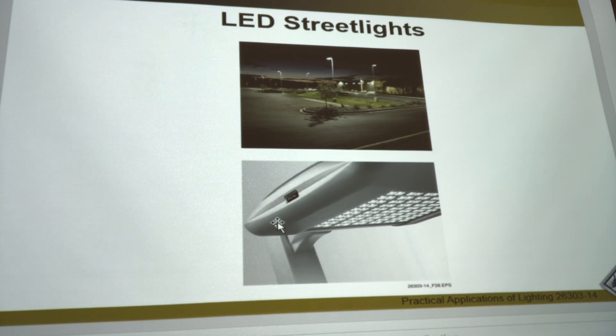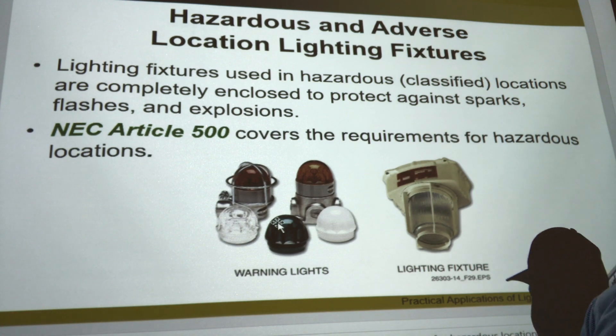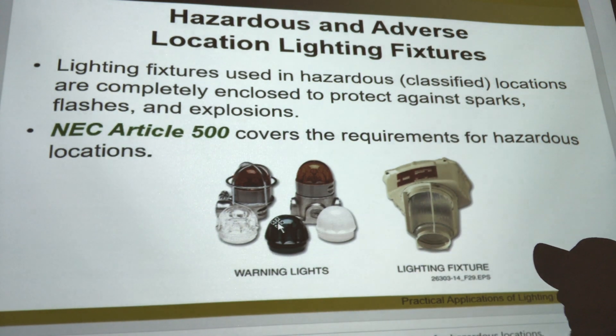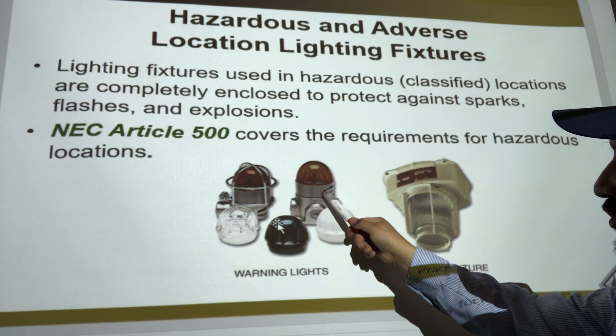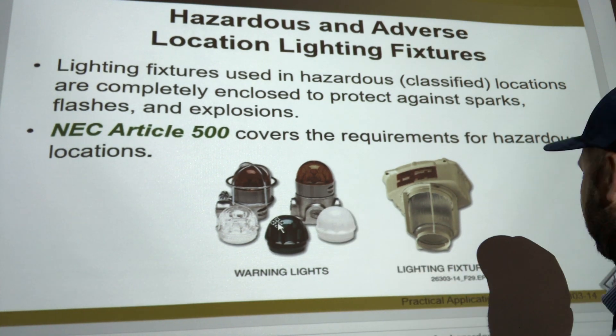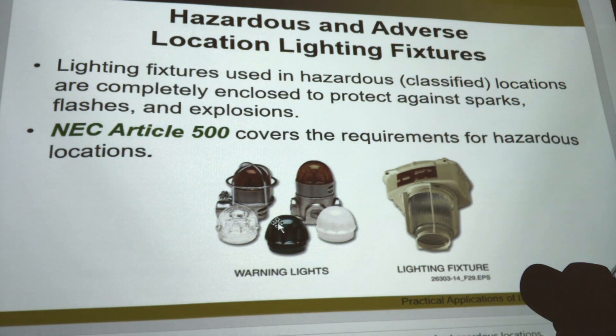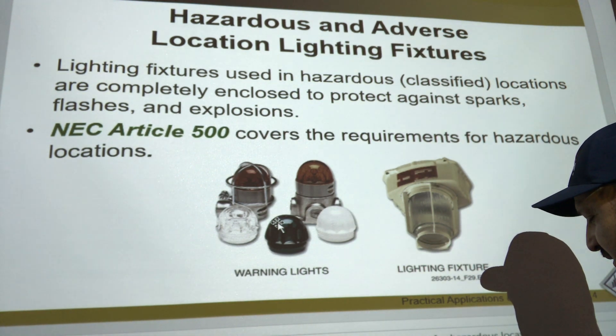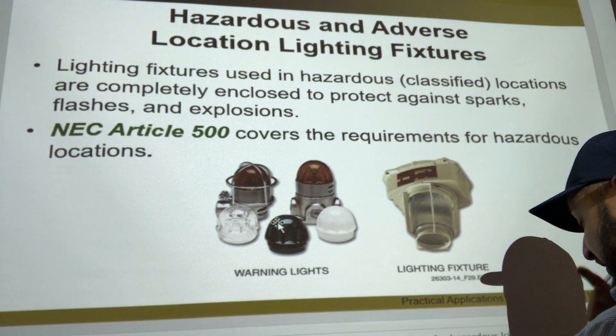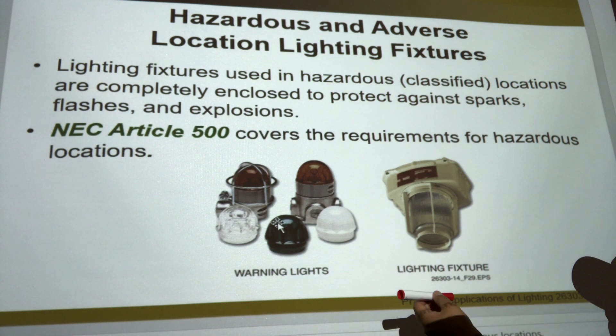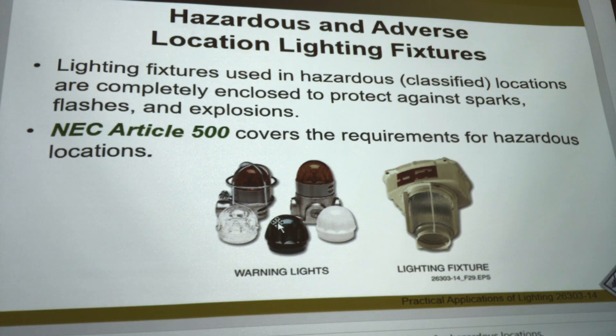That's where foot candles and lumens come in. We also have special hazardous location lights used in industrial areas — the glass is super thick and made for explosion-proof environments. You screw the cover on and run rigid conduit through it. Use these for paint booths, wood shops, freezers, and AC rooms. Article 500 is really important — it covers hazardous locations. At gas stations, for example, everything 18 inches below grade has to have rigid conduit.